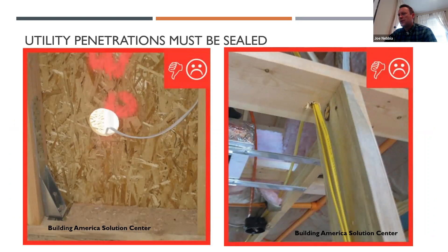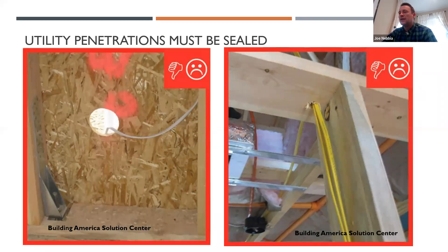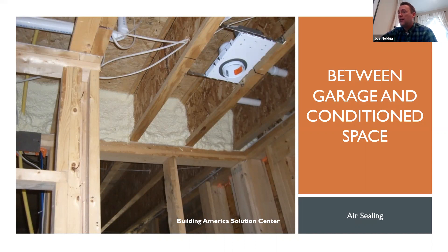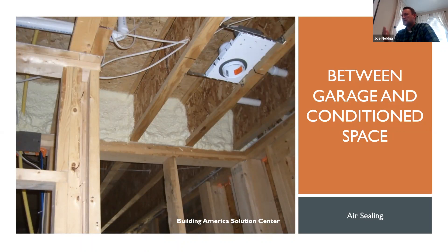All penetrations through the envelope must be sealed. On the left, you see a big hole with a wire going out of it — hopefully that was caught before the home was finished. On the right, you see wires going into an attic space; that needs to be sealed before the air barrier inspection, because you could have air leaking from the attic into the conditioned space. Conditioned space and garage junctions have to be air sealed. Here we see spray foam between those spaces — it doesn't have to be spray foam, it could be solid blocking with caulking at all the joints. We don't want a floor cavity where the garage is cold and the inside is heated and air is just moving between those two spaces.